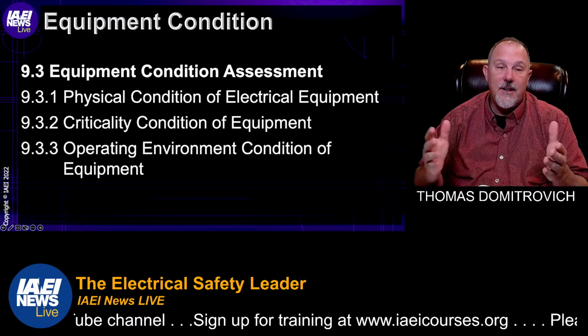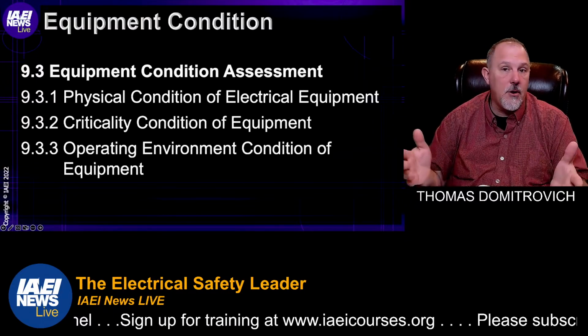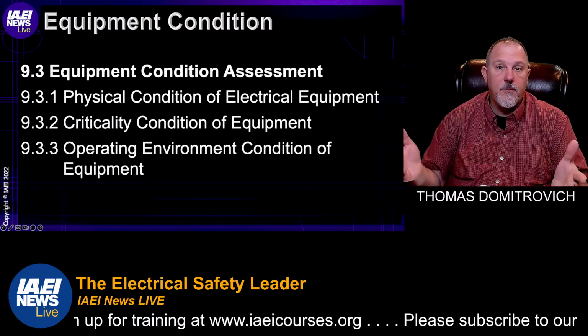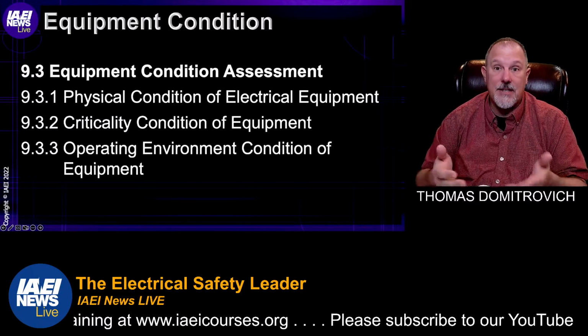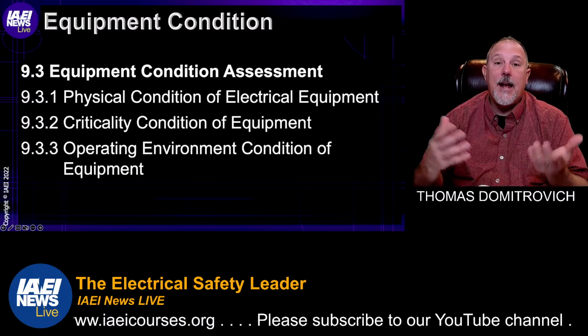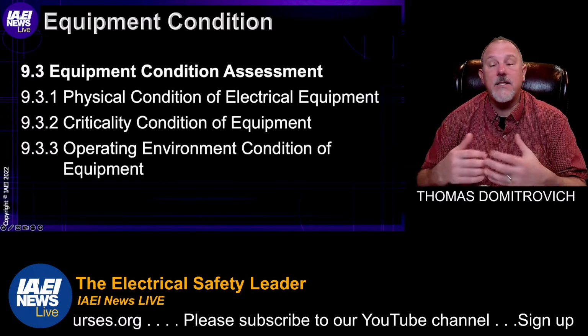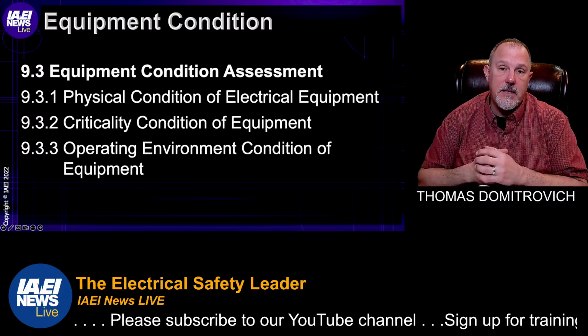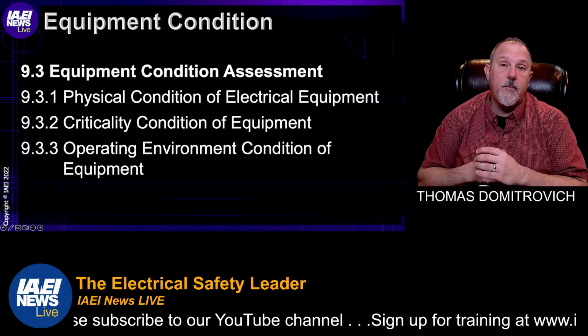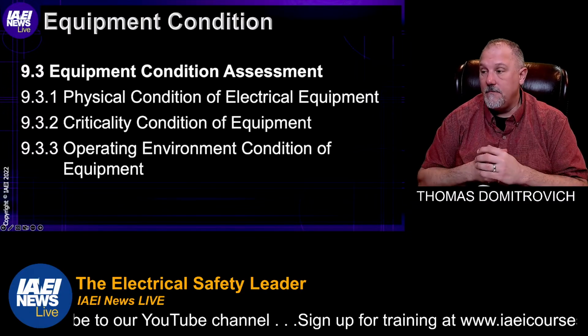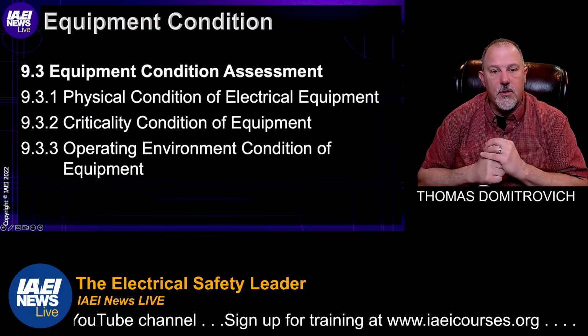So maybe I've got high temperature alarms or high humidity alarms that have not been addressed, because there is currently high temperature, high humidity, and it's been persistent and it hasn't been addressed. Well, maybe that's an indication. Maybe there's a trip breaker in there that hasn't been addressed. So that's the physical conditions.